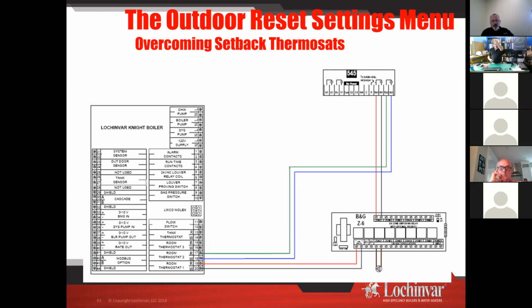So we have the ability there to take a 2-stage thermostat. Basically, the first stage call, I don't know why I'm clicking on it with my pointer here. Doesn't do you guys any good. My first stage call comes right over here. It's going to turn my pump on. It's going to turn my boiler on. When I need that second stage call, when I'm coming out of that night setback, here's what I'm going to do. It's going to go over here and tell my boiler, hey, raise the water temperature. Whatever you set it for. Maybe this is a fixed 160 or 170 degree number, whatever it is.